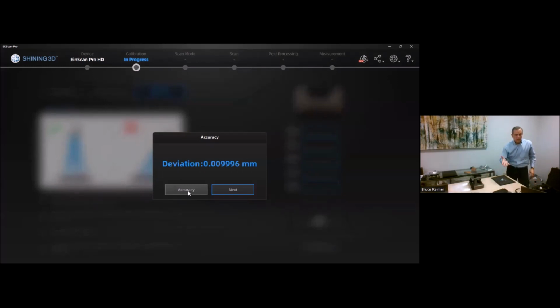So it's giving us an answer. It's saying that the deviation is 0.009996 millimeters, essentially 10 microns. The comparison threshold is 50 microns or 0.05 millimeters. So as you can see, we're well below that. We've got a good calibration. We can proceed with confidence, and we're ready to go scan some parts.